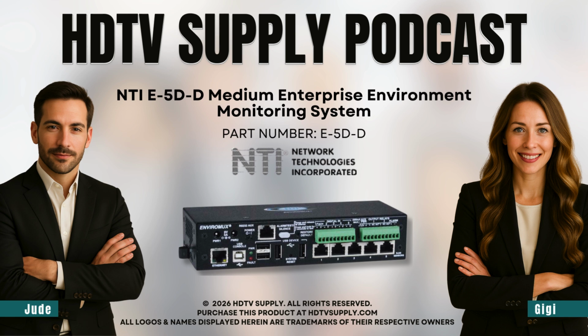What about reliability? You can't have your monitoring system go down. That's paramount, it has dual redundant power supplies that switch over automatically if one fails. There's also an optional internal battery, so it can still send a power-out alert even when the lights are completely dark. You can cascade up to 5 units as slaves to one master, getting a single unified view across different locations.